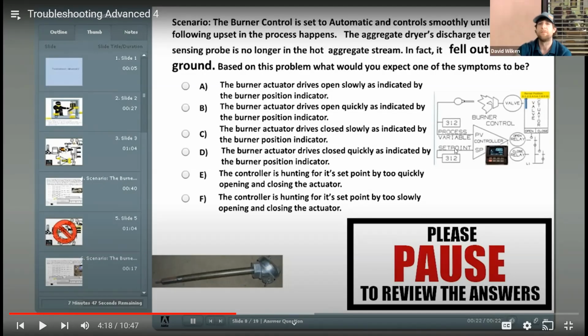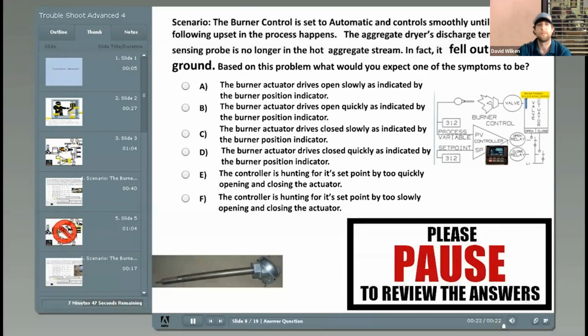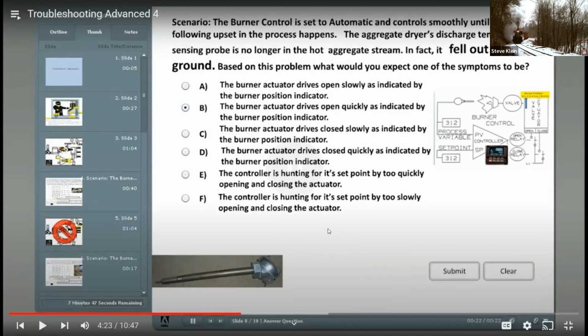If our temperature probe fell out on the ground, so it went from 312 degrees to 70 degrees, do you think it's going to be hunting? No, it'd probably drive open quickly. Yep. Now, I'm going to be a really nasty person, poke holes in this. If the temperature probe fell out on the ground, quite often, I don't care. It's charting on the chart for the state. That's the only reason it's important. I'm controlling off my stack temperature. For purposes of the question, though, you're controlling off the material probe.